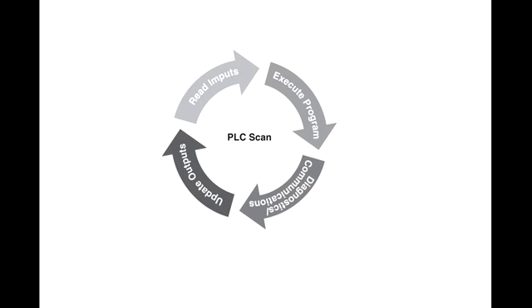PLC scan. The scan starts with the CPU reading the status of inputs. The application program is executed using the status of the inputs. Once the program is completed, the CPU performs internal diagnostics and communication tasks. The scan cycle ends by updating the outputs, then starts over. The cycle time depends on the size of the program, the number of inputs or outputs, and the amount of communication required.